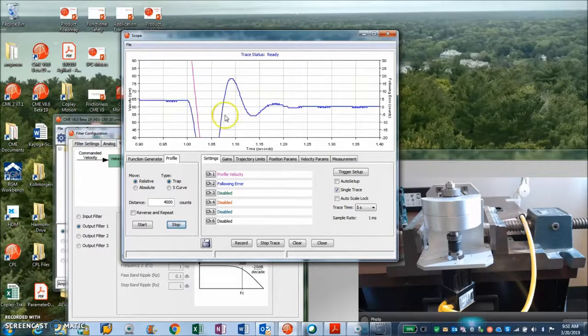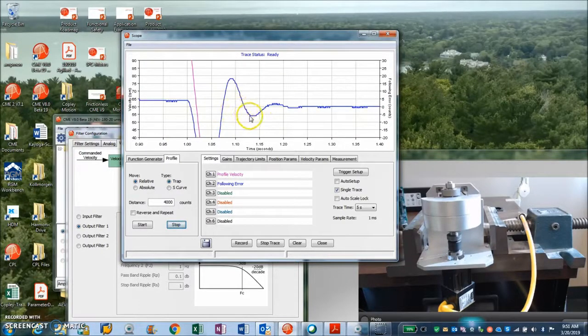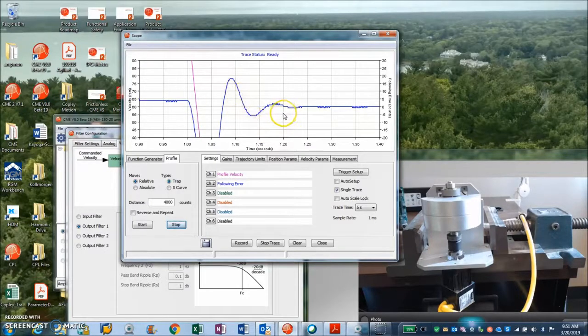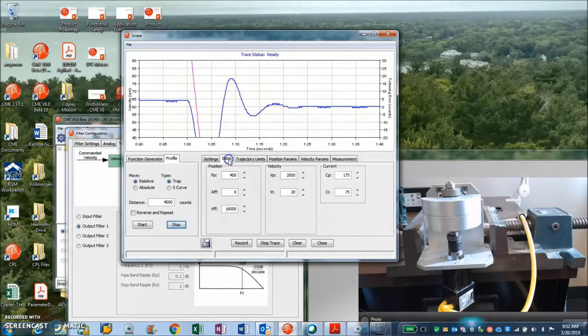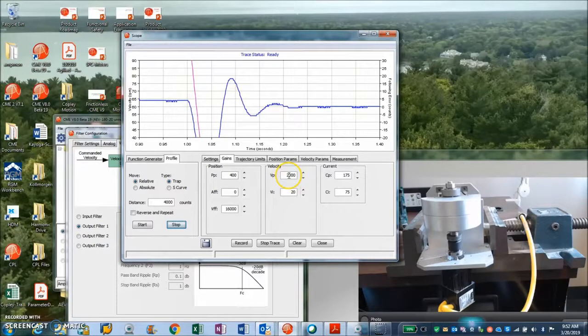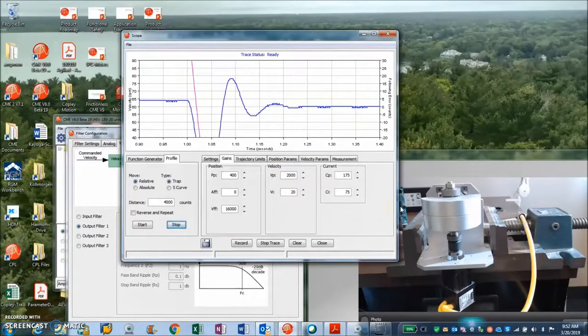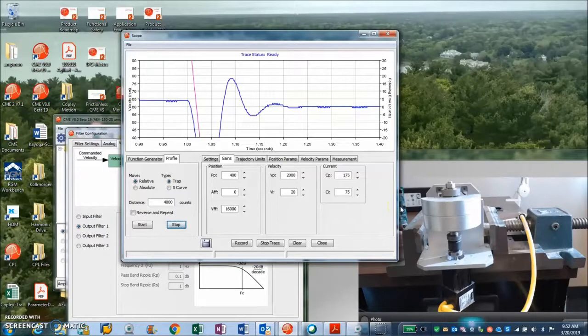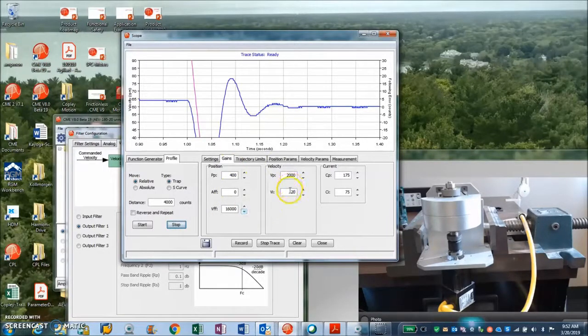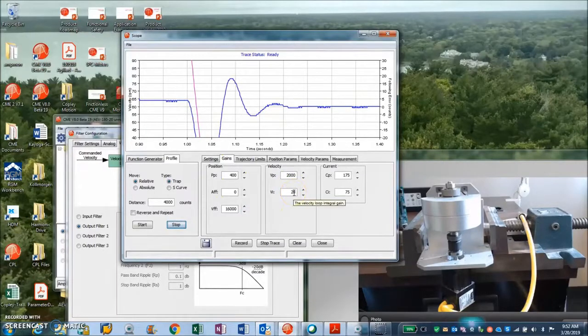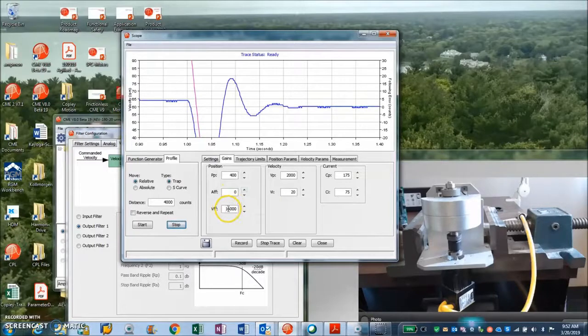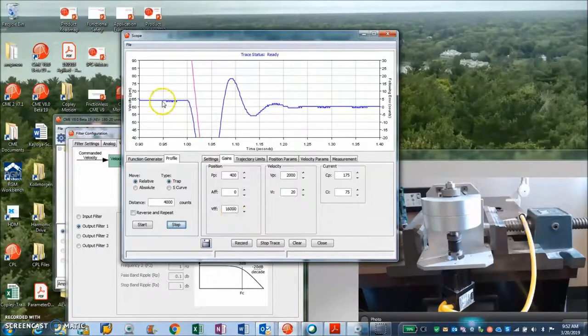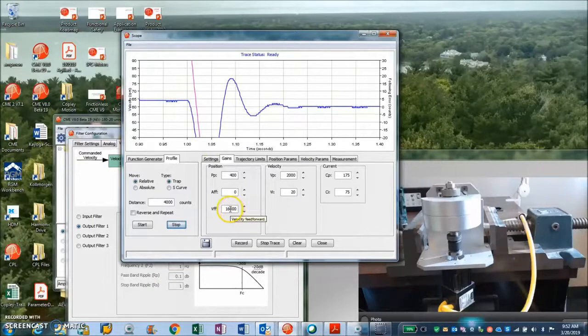So my settling time is pretty quick—a nice frequency. Again, it's based on the velocity loop stiffness, the electromechanical time constant, and the amplitude is the proportional gain. So we're far away from oscillation. If the gain—you know, we double it and double it, we might get oscillations. Always cut it in half, give yourself some gain margin. Integral—no integral wind-up, keeps it nice and low. Large inertia, it's usually a small integral. No need to worry about the feed-forward term—that's just the error while it's moving. 16,384 is the default.